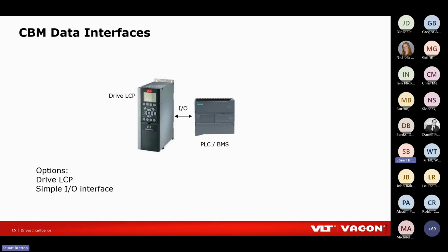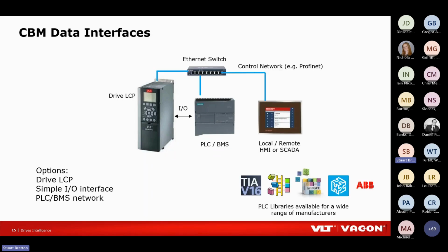Maybe we'll connect some outputs to a PLC or a BMS system. We could configure a digital output on the drive to tell a PLC or a BMS, I've got a problem with the vibration sensor, or I've got a problem with the stator winding on the motor. That's quite a simple interface. We might extend that and say, well, our drive's got Ethernet on it or some sort of field bus. Why not network that up to a PLC of some description? Maybe we'll even take that data out to a SCADA system or an HMI.